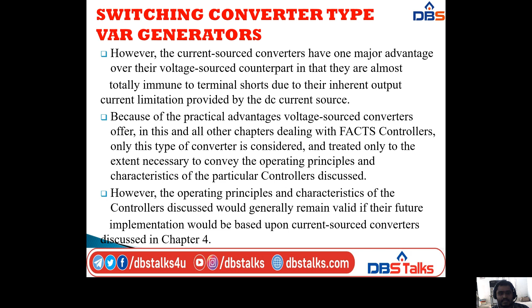Next, the basic operating principles in switching converter type reactive power generators. The basic principle of reactive power generation by a voltage converter is akin to that of the conventional rotating synchronous machine, shown schematically in this diagram, used for reactive power generation by a rotating synchronous compensator, also called a condenser.